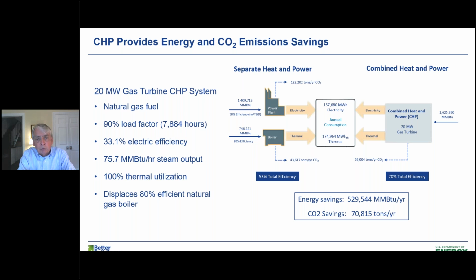I'm basing the discussion on a 20 megawatt gas turbine CHP system, natural gas fueled. It's very typical of what you would find in an industrial application. It operates at 90% annual load factor, or capacity factor—7,800 hours per year. It has a net electric efficiency of just over 33%.